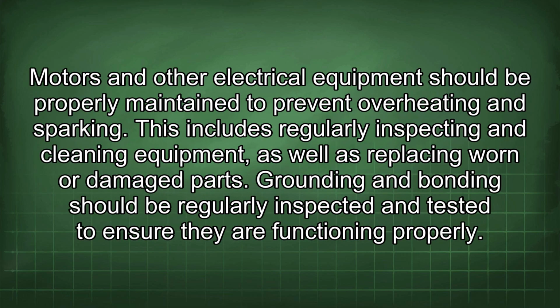Motors and other electrical equipment should be properly maintained to prevent overheating and sparking. This includes regularly inspecting and cleaning equipment, as well as replacing worn or damaged parts. Grounding and bonding should be regularly inspected and tested to ensure they are functioning properly.